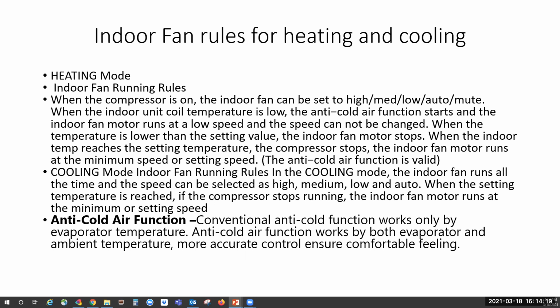Indoor fan rules for heating and cooling. This is pretty much straight across the board. It does change a little bit when you get into the ducted systems, so you might refer to the service manual for that. Basically, in the heating mode, when the compressor's on, the indoor fan can be set for high, medium, low, auto. When the indoor unit coil temperature is low, the anti-cold air function starts, and the indoor fan runs at a low speed. This speed cannot be changed.